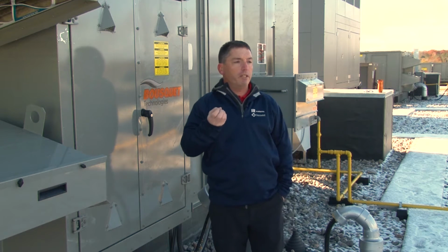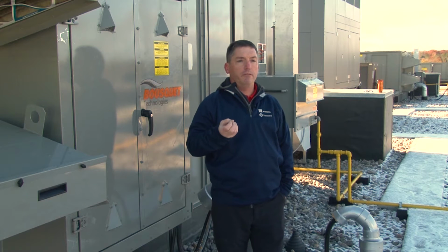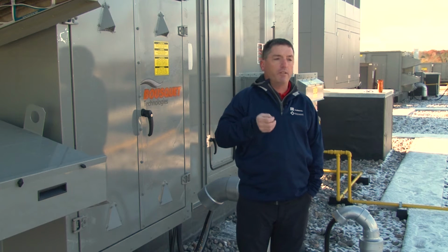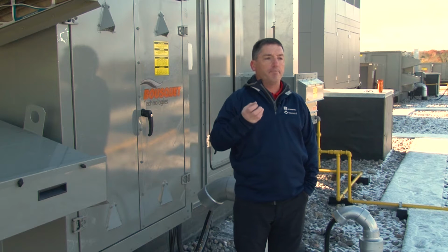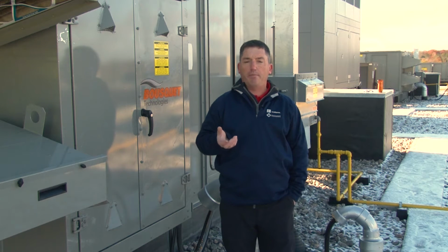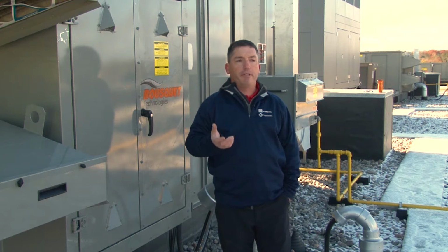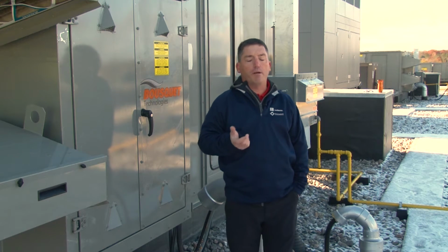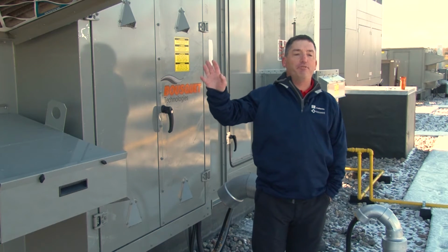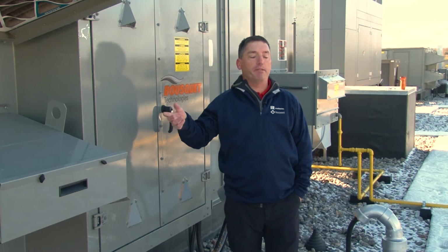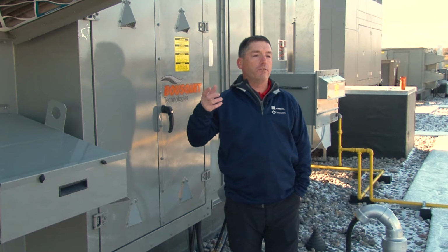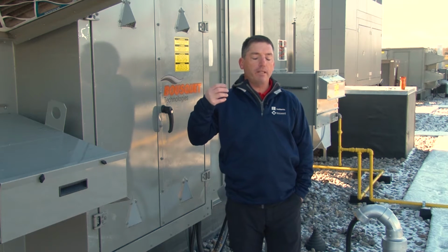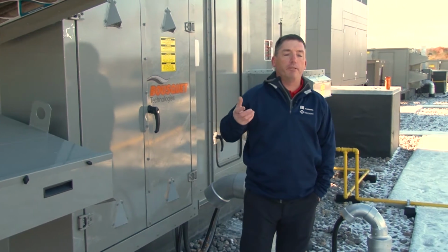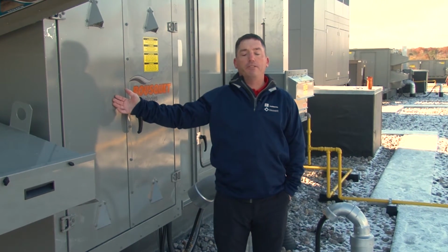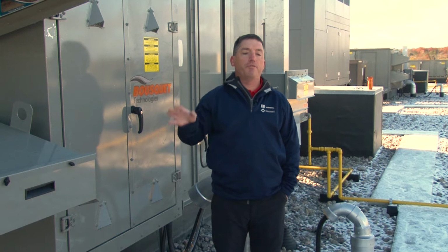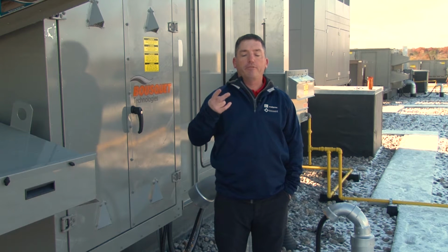It's made of a corrugated aluminum material, so as far as longevity, unless it gets some extreme physical damage, which is a very rare case, it should last for upwards of 20 years. If you find that the filters aren't being maintained and you start to notice extra dirt being brought into the building, or if during a maintenance inspection you notice that the surface of the wheel is starting to get dirty, you have 2 options.